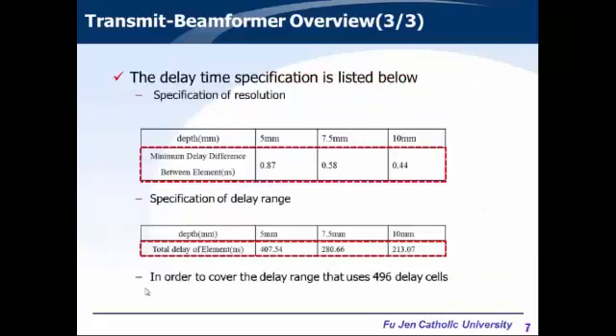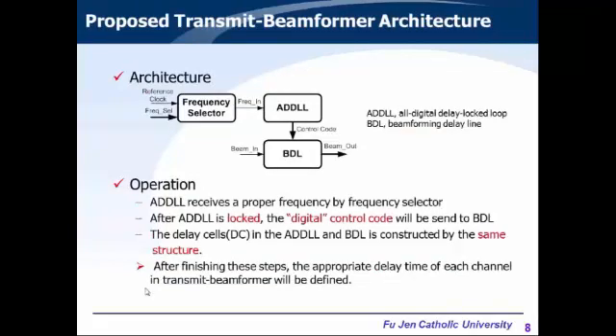We can transform a delay table to a multiple-integer delay in MATLAB before designing the transmitted beamforming. Our proposal includes three main blocks: Frequency Selector, All-Digital Delay-Locked Loop (ADDLL), and Beamforming Delay Line. First, ADDLL receives a proper frequency from the Frequency Selector. After the ADDLL is locked, it generates a digital control code to the beamforming delay line. The delay in the beamforming delay line is then determined because the delay cells in the beamforming delay line and ADDLL share the same structure. As a result, the delay of the transmitted beamforming can be determined.